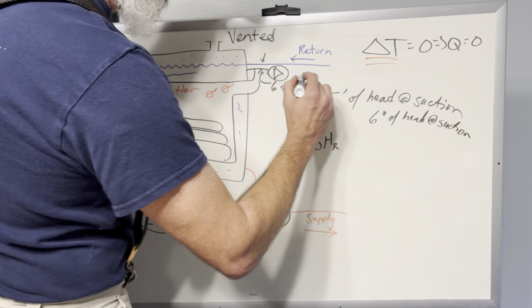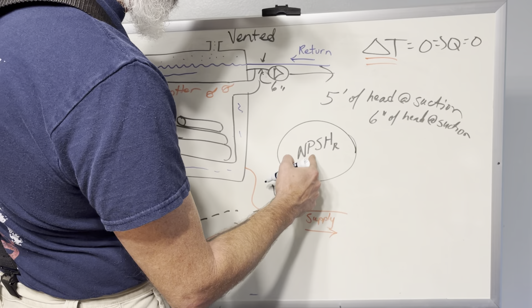Depending on how much flow you need that way, your pipe size and stuff like that, most of the time that's going to start causing you problems because you don't have enough net positive suction head. So just some food for thought for you.